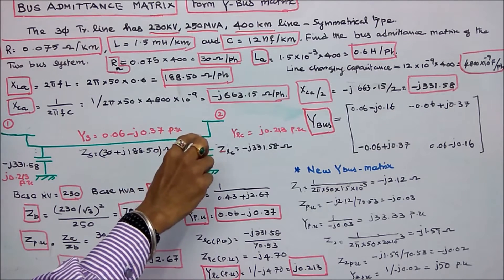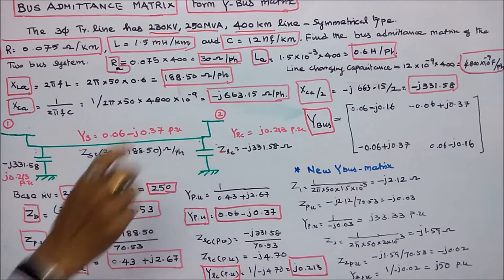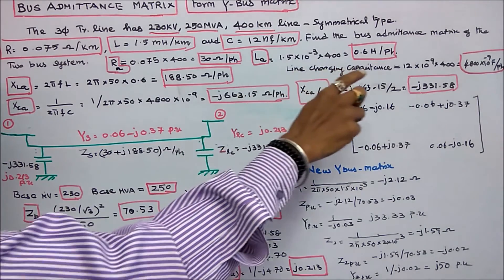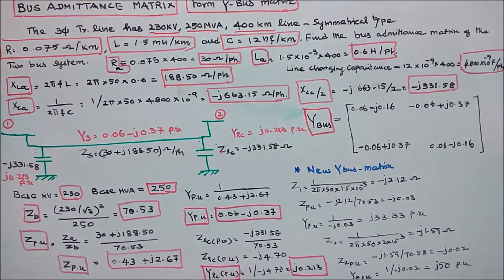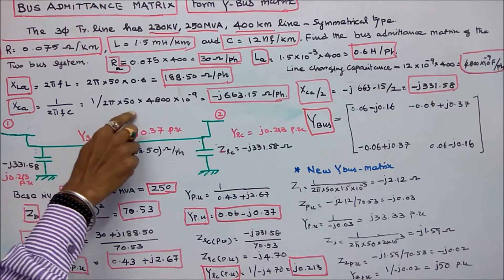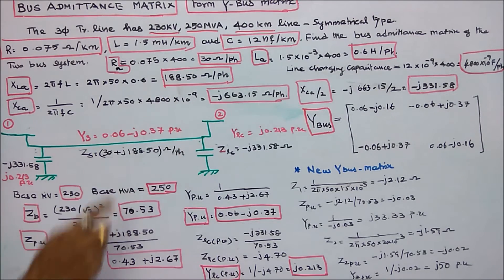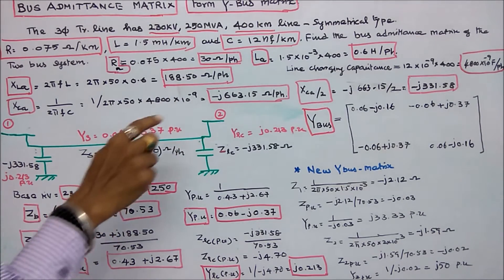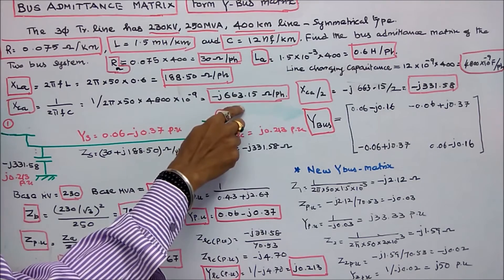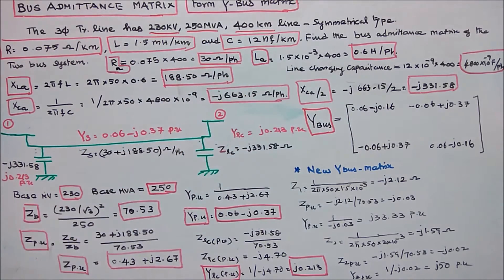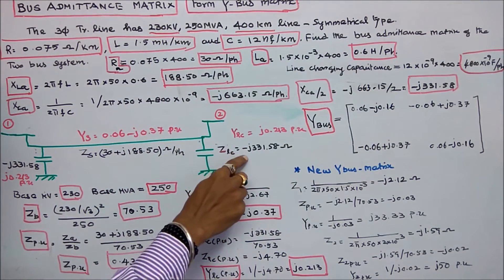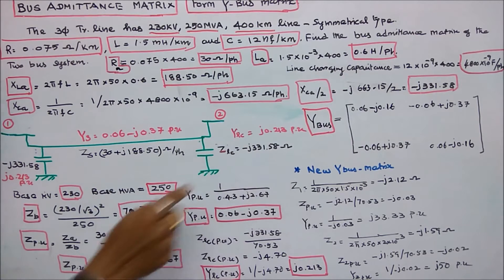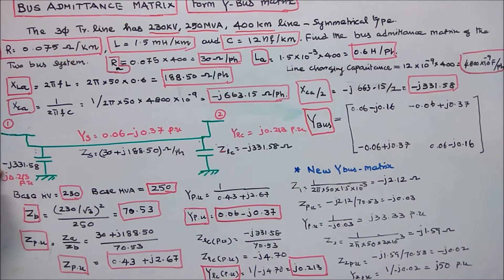The line charging impedance is 1 / (2π × 50 × 4800 × 10⁻⁹) = −j663.15 ohms per phase. Divided by 2, that is −j331.58 ohms per phase for each shunt element.